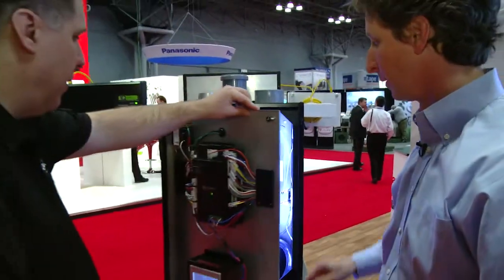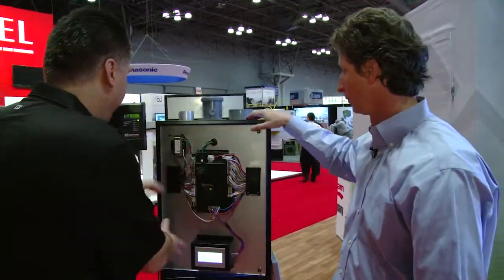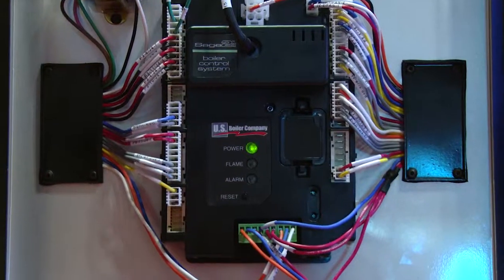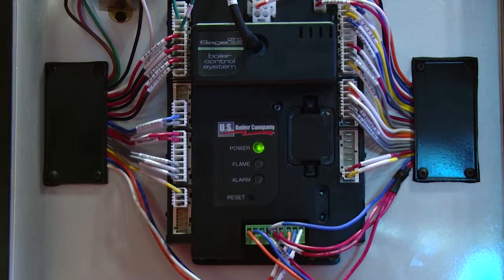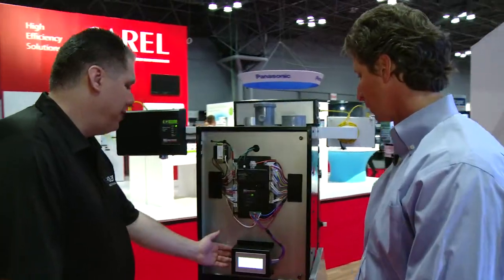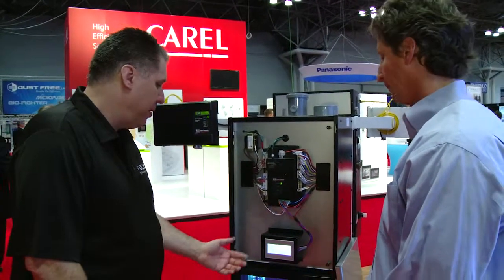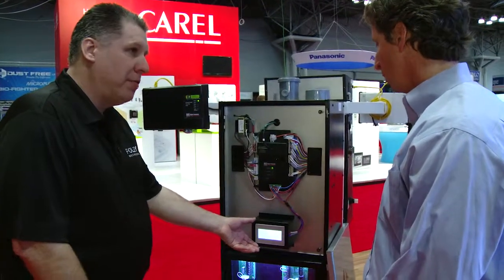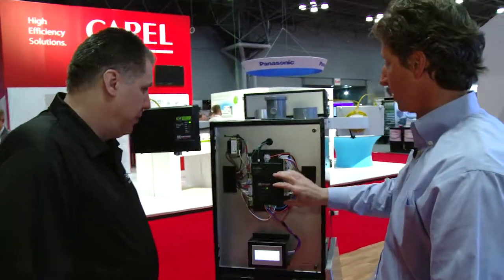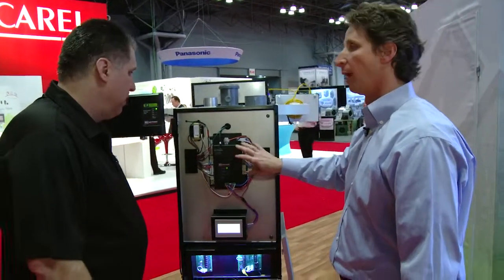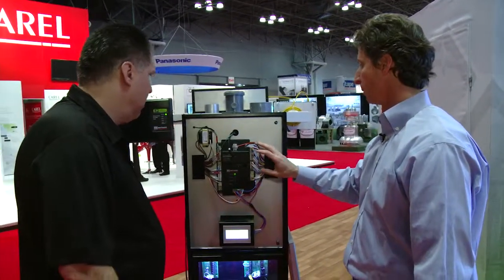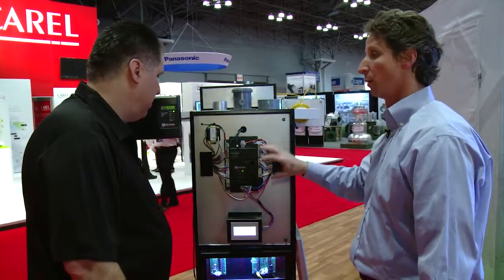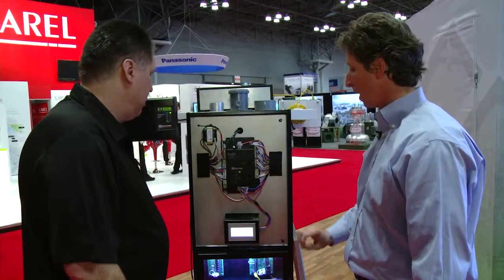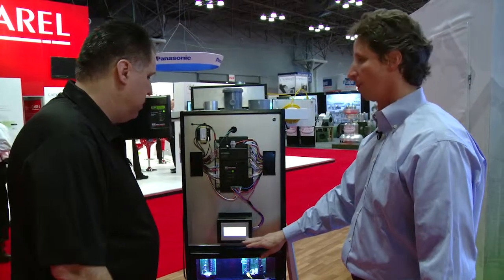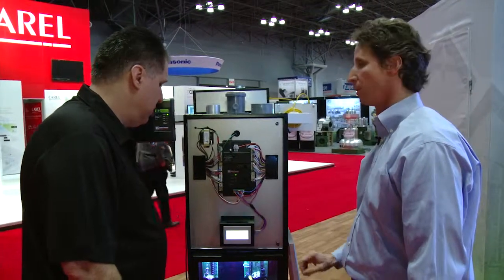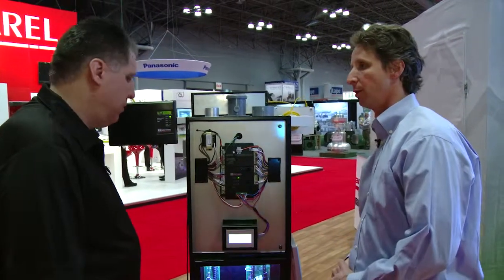Chris, a couple things I like: I like that you separated the controls from the combustion chamber. That's been an issue with us on several products we've worked on. I also like that the control is isolated from the combustion products. Is this the Sage control I'm used to, or is this different? This is absolutely the Sage control you're used to. We're actually on Wave 5 of the software now. It's a set of proprietary software coding, although it's a standard piece of hardware from Honeywell. We continue to use the latest version of the Panasonic display, a higher definition display you may have seen on some of the older Alpines you would have put in.